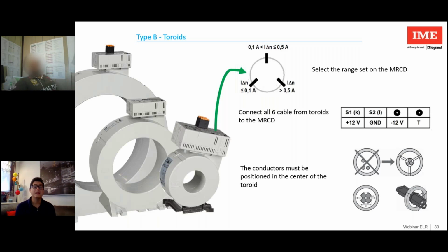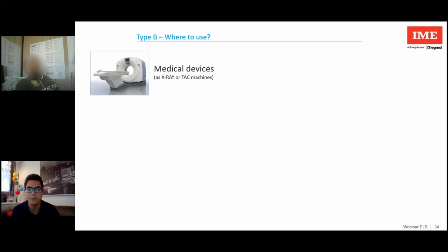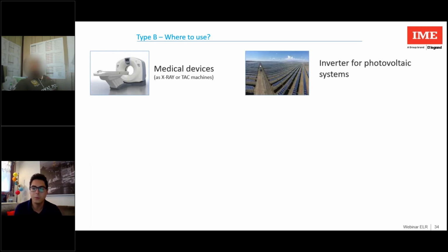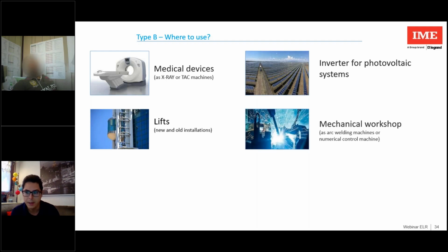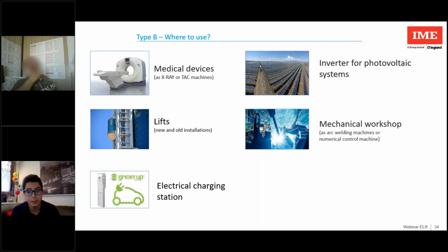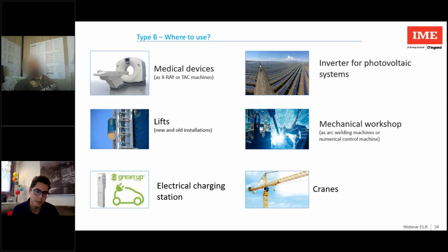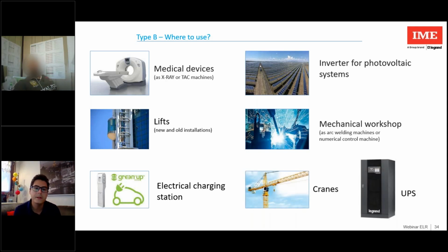Well, where can I install this type B? Wherever there is a possible continuous component that can distort the waveform. Some examples are medical devices, the most common inverters for photovoltaic systems, lifts, welding machines, as I said before, electrical charging stations, cranes, and last but not least, UPS. So in every single case where a continuous component can deform or add a component to the waveform of the alternating current signal.